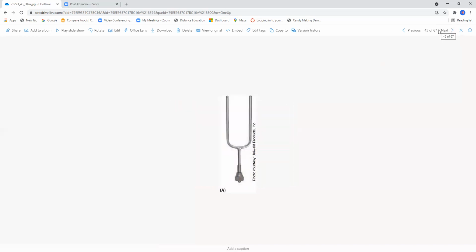Okay, this is not a tuning fork. This is actually a special type of welding tip. Basically, you would hook it up to your oxyacetylene torch handle, and you would have a flame which comes out of this side, a flame that comes out of this side. Now, in theory, if you use this fork heating mechanism, it applies heat evenly across the joint, but it takes special practice to operate and utilize this tuning fork torch tip. I do not personally use these in my business. I find that they're more of a hassle than they're worth, but this is one method that you can utilize when you are installing reversing valves to apply heat evenly.